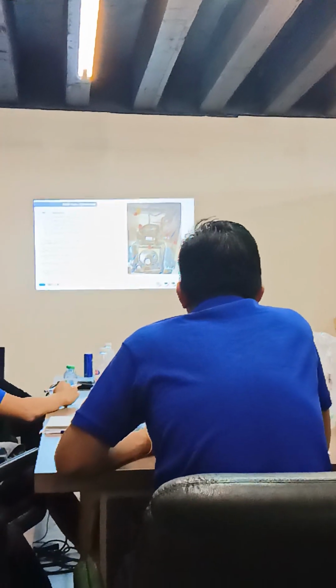The suction pressure for R404A is between 21 and 55, with a 3 differential, and for 290 it's 7 to 34 psi. And the high pressure cutout is activating at 425 psi.